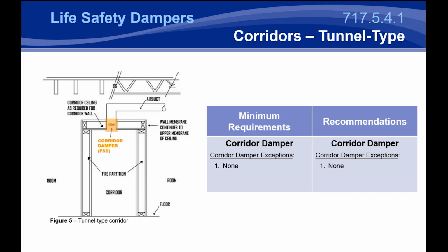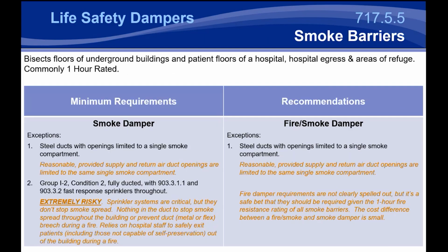They're widely used in California. They aren't really used throughout the nation, but it could pose a potential risk to architects that see this horizontal framing detail and call that out in non-tunnel type corridor applications. There's really not a lot you can do for these other applications that are not these non-load bearing tunnel type corridor applications. I'm going to get into what you can do to protect a floor opening or a through penetration when you're installing a damper horizontally in a little bit, but I'm going to talk about smoke barriers first.